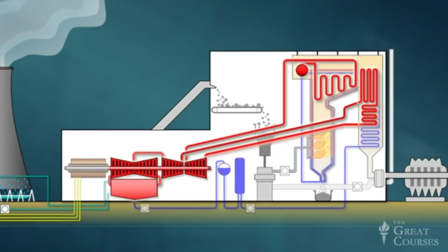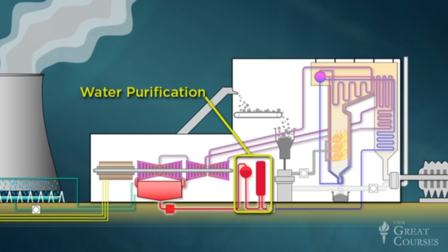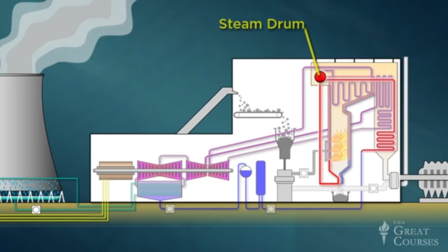Water collected from the bottom of the condenser will eventually be recirculated to the boiler to complete the so-called feed water loop. But before this can happen, the feed water is intensively purified to remove rust particles, dissolved minerals, dissolved oxygen, and acidity, all of which can foul the riser pipes or promote deterioration of those critically important turbine blades. The purified water is then pumped through a device called an economizer here, which extracts even more waste heat from the flue gases, and then back into the steam drum, where it rejoins the flow of water through the downcomers to the boiler. But the job of extracting energy from those flue gases still isn't done.